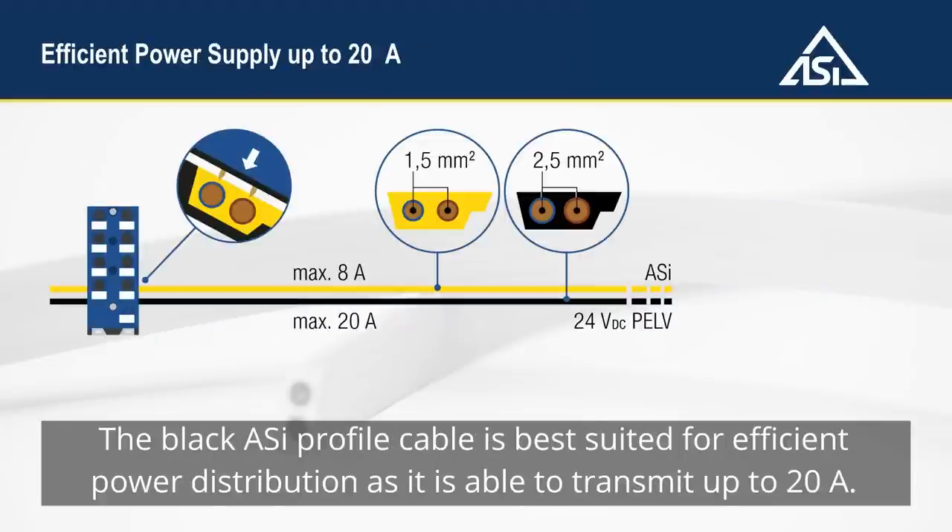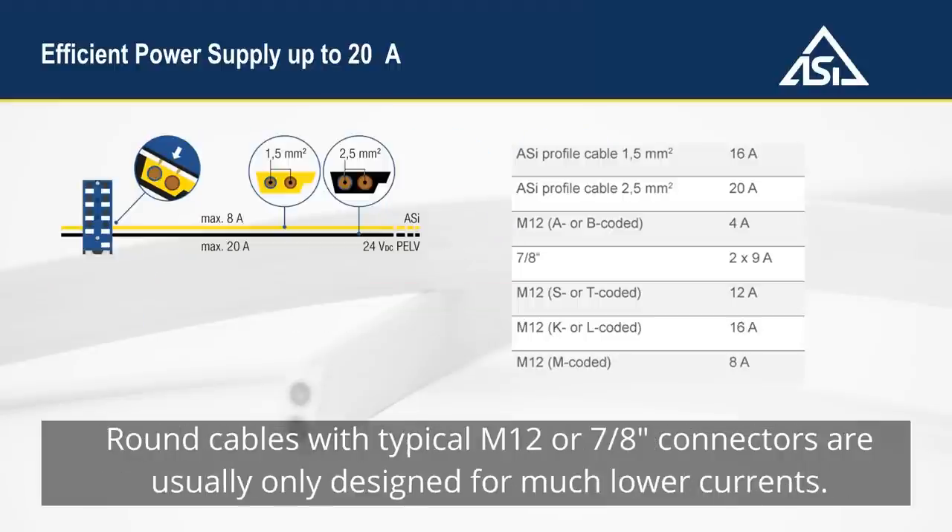The black ASi profile cable is best suited for efficient power distribution, as it is able to transmit up to 20 amps. Round cables with typical M12 or 7-eighths inch connectors are usually only designed for much lower currents.